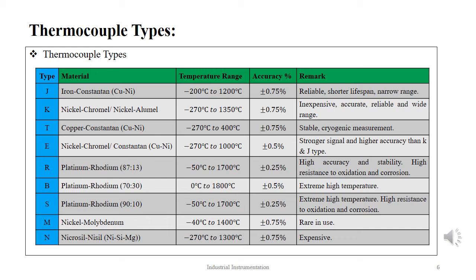The thermocouple types are based on the metal alloy combinations for the two junctions. These metal alloy combinations are chosen to match different requirements like temperature range, sensitivity, inertness, and magnetic effects. There are mainly 9 types of thermocouples based on the material compositions, namely J, K, T, E, R, B, S, M, and N. Other than these 9 types, there are also the C, D, G, P, and W types. The temperature ranges of each of these thermocouples vary because of their composition as well as their accuracies.